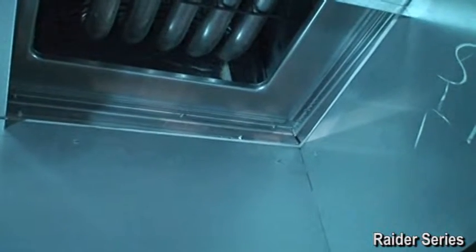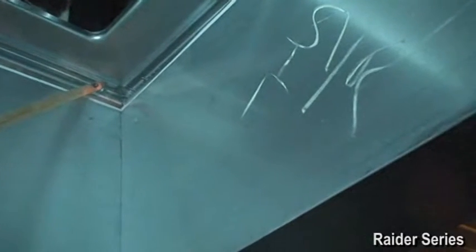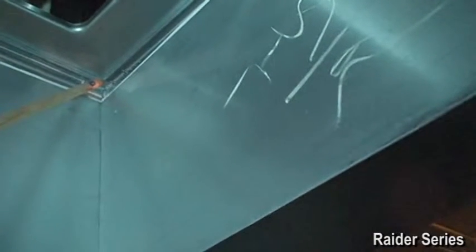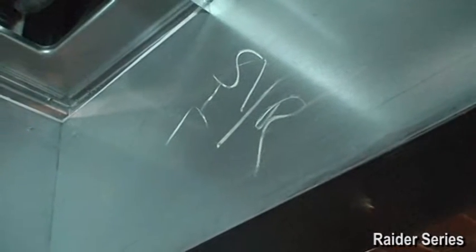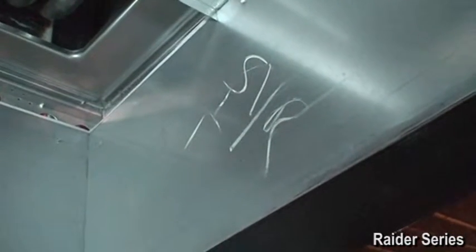The first thing noted with the competitor's design was that it was not as forgiving or intuitive as it is led to be, and it did not fit on the curb with proper alignment. As seen here, there are metal lips hanging down, and if they are not directly placed properly, they would rest on the curb and create air and water entry. This can also be further magnified when you think of real-world conditions when placing a unit on a curb. You can have windy conditions from the weather or a helicopter. Plus, you do not have the luxury of being able to see under the unit as shown here.